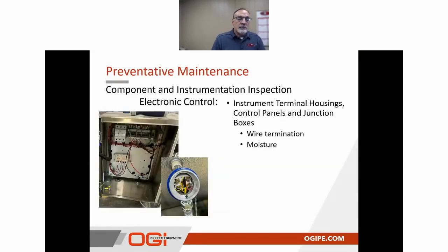For the electronic control systems, we want to open up all the electronics housings and make sure that the terminations are good, and that we're not seeing any moisture or potential corrosion inside of these instruments. That includes control panels. If we're seeing condensation, it may be warranted to request or locate some desiccant bags to put inside of those control panels to keep them dry.